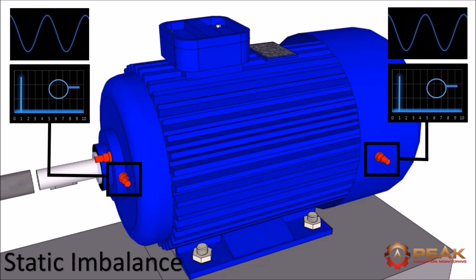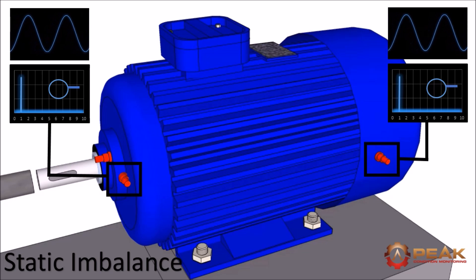A static imbalance would show the waveforms measured radially at each end of the motor to be in phase as shown here.